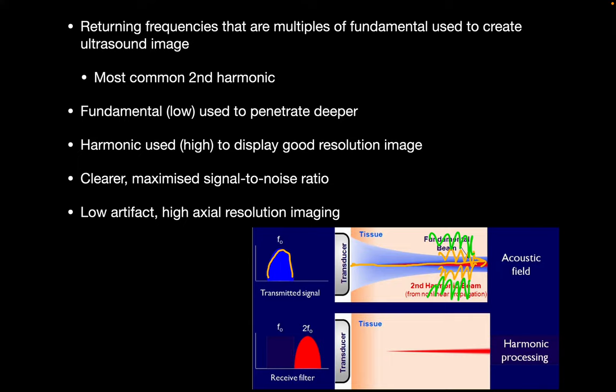So these modern ultrasound systems, they use the fundamental frequency to transmit into the tissues, and then they're gonna use the harmonic frequency to get the information back from the tissues. So they're gonna be listening in these multiples of the base frequency, and that's gonna give you a nicer image.